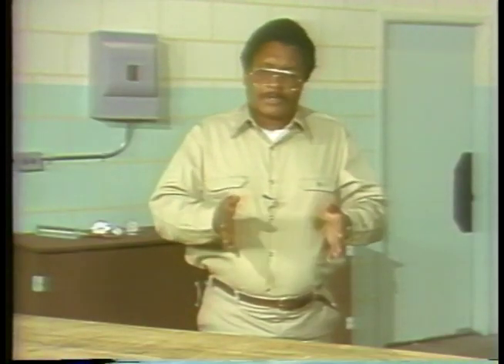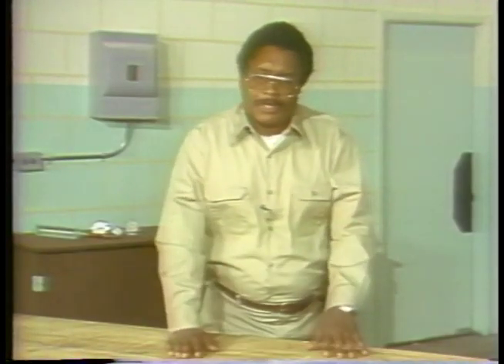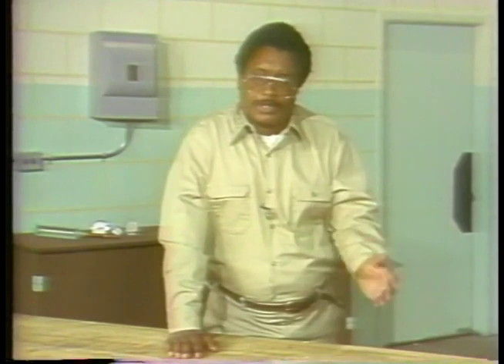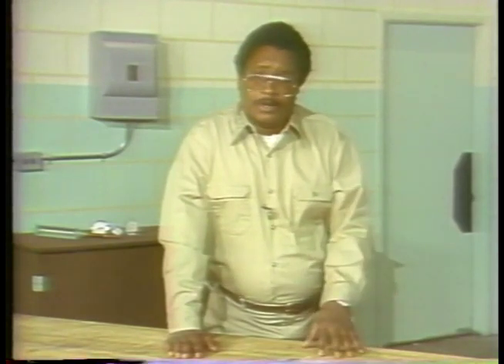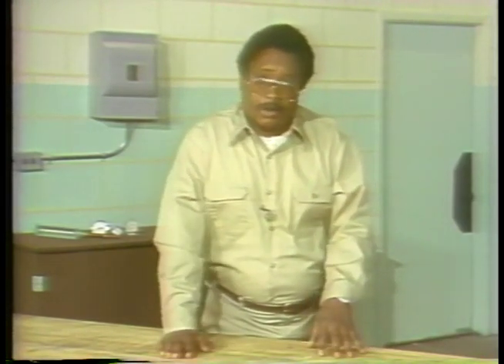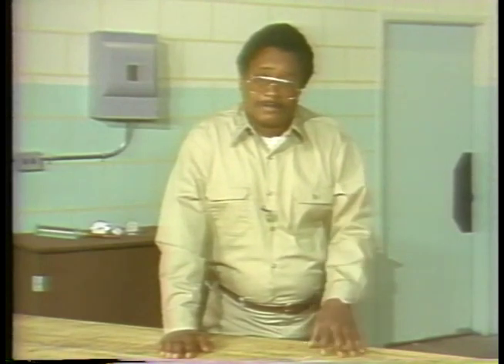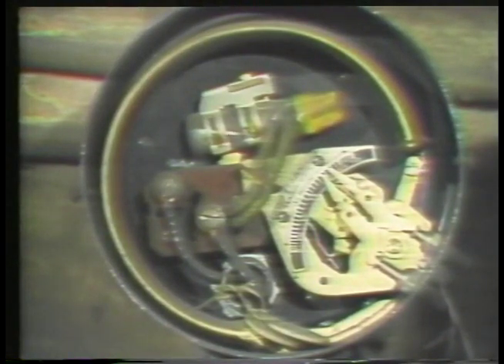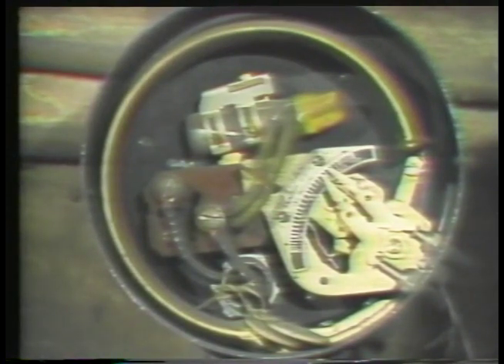As you know, pressure sensors can be connected to transmitters for remote indication, or they can operate switches that initiate alarms or turn equipment on or off. The same is true for pressure sensors used to detect level. For example, this Bourdon tube pressure sensor, which is being used to measure level in a condensate storage tank, operates a mercury switch connected to the Bourdon tube by a mechanical linkage.